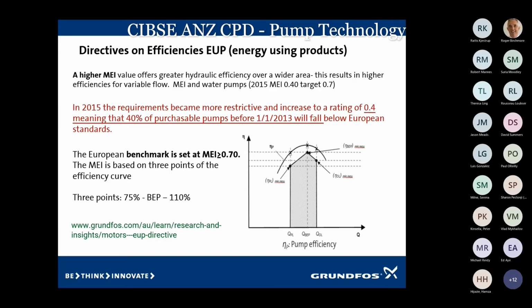The efficiency we mentioned before in Europe under the EuP directive, which Grundfos and a number of other European manufacturers must meet, was brought in a few years ago for the hydraulic efficiency. They take a measure, and what they do is they'll take the peak efficiency, the best efficiency point, 75% of the best efficiency and 110%, and they'll make a calculation, and that comes up to a figure, and it was 0.1. The EuP directive was to change that in 2015 to 0.4.